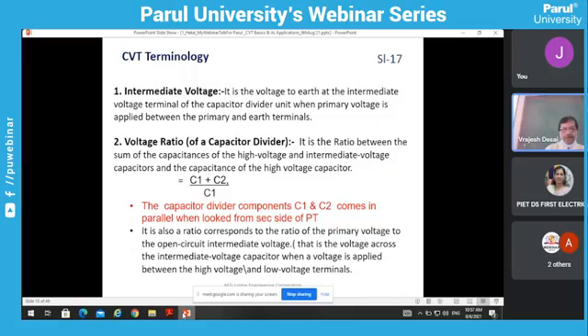So just to start, how the concept has taken place some 50, 60 years before. You will have an idea that capacitor means everything is made of capacitors. So we try like this from two sides across the line, but it has its own limitations because the current which is fed by it is very small. This is very less. Our system requires for burden 100. So we have to take this to a higher voltage.